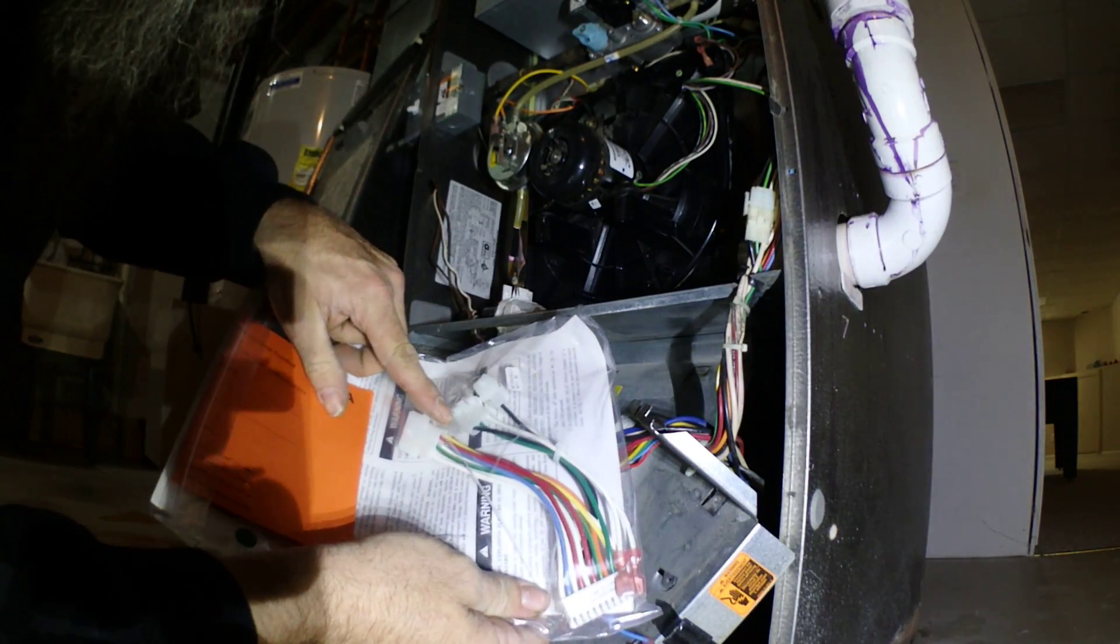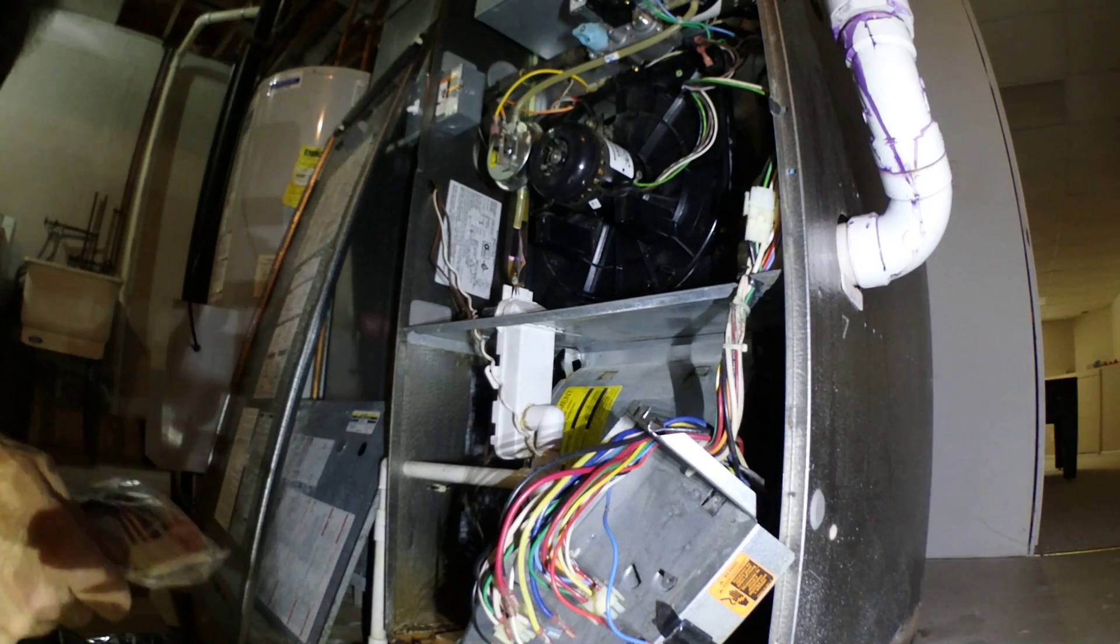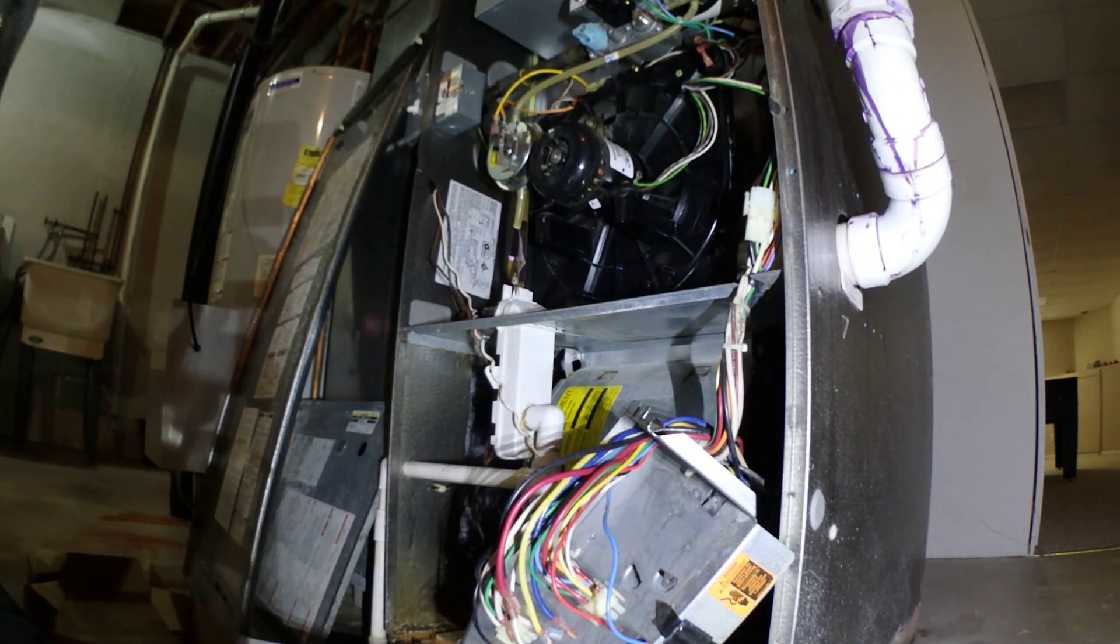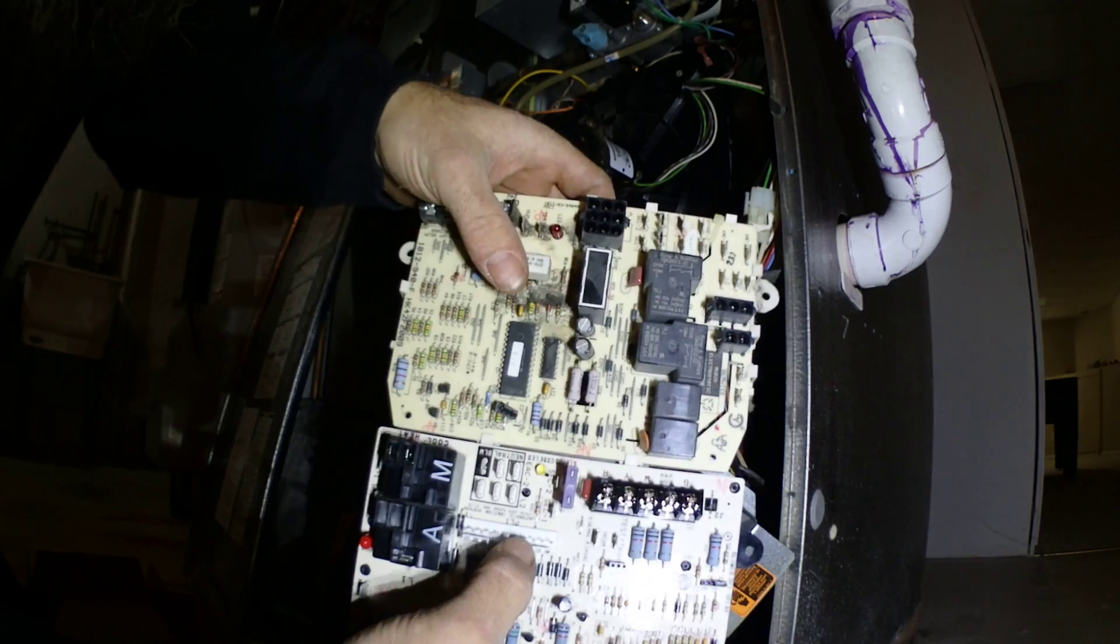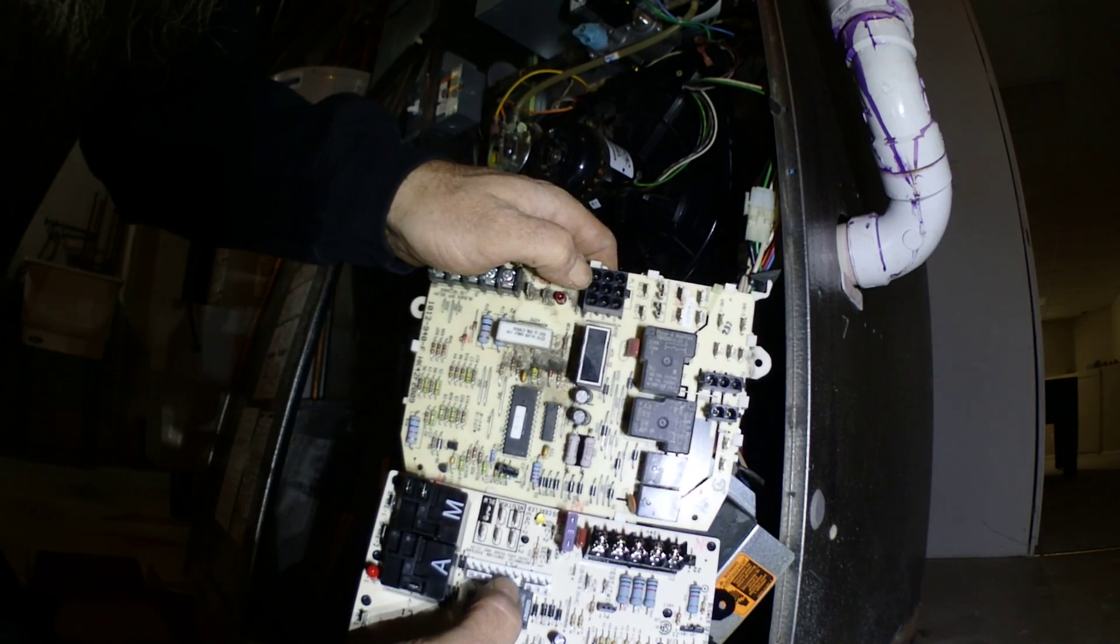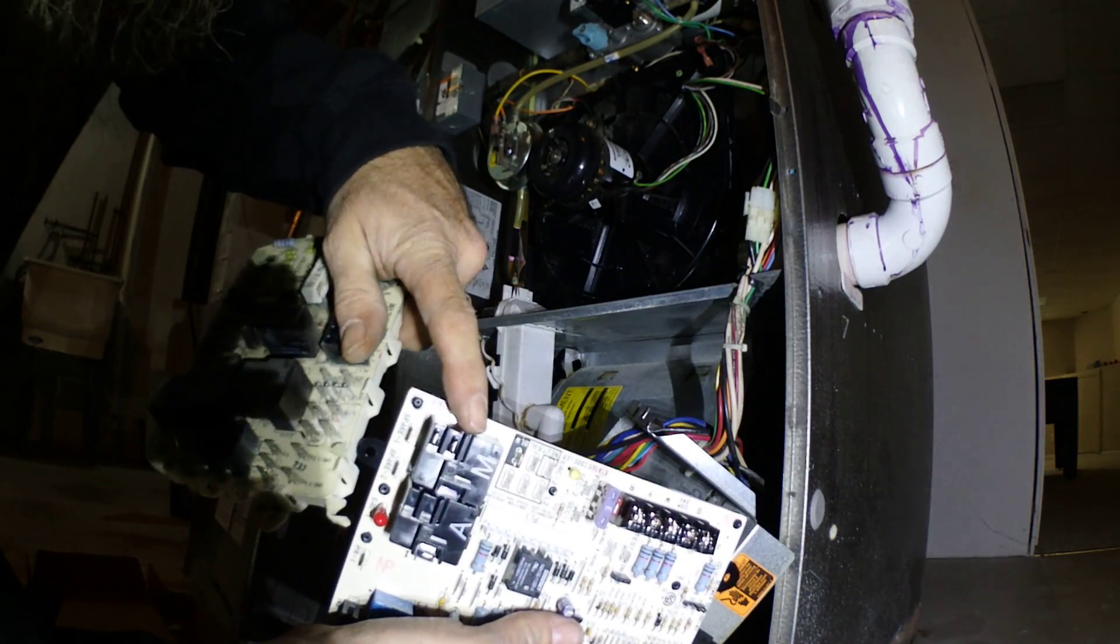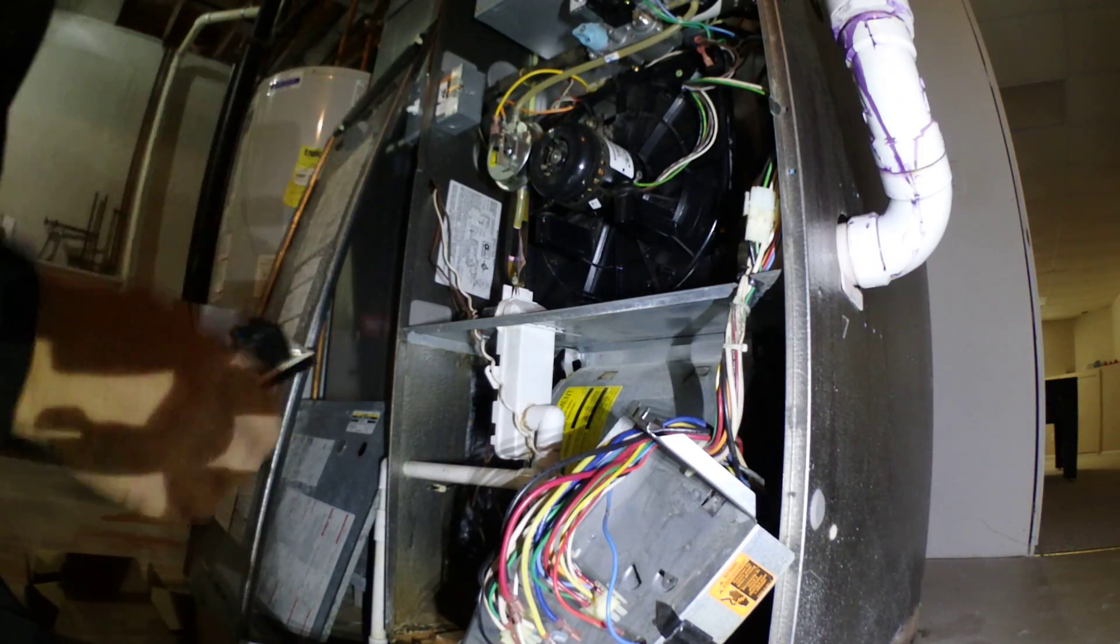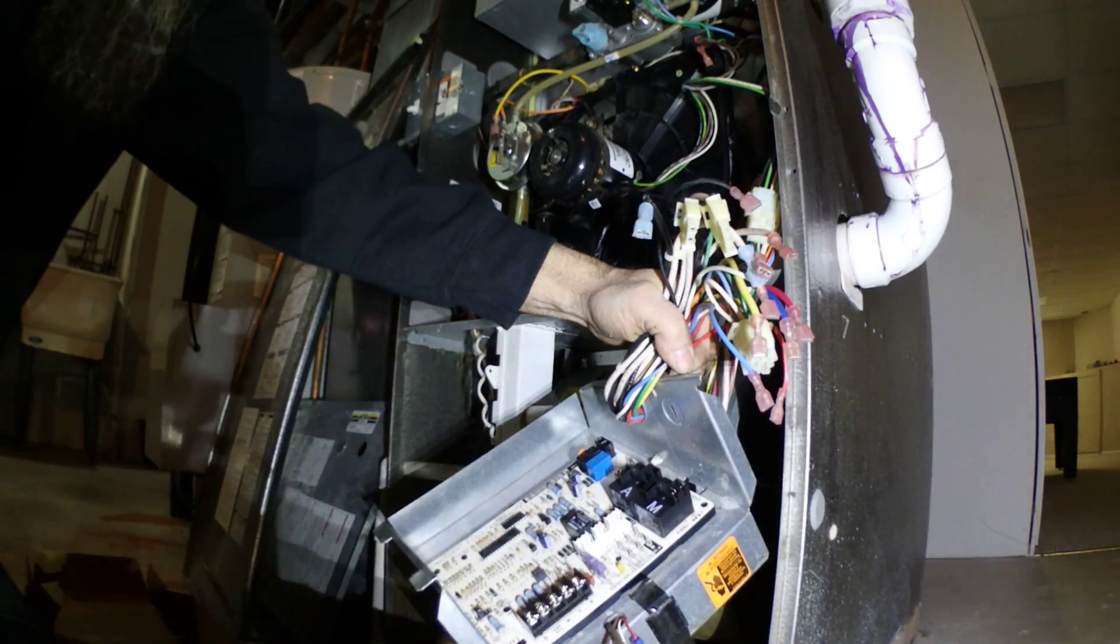Okay, this is a retrofit kit so it comes with a harness. Plugs into the board. Got two neutrals, two hots there, or a plug for a hot. Here's the new board, here's the old board. See how it has that plug? This one has that plug. So then my old one, my speed taps are here. New one, the speed taps are here.